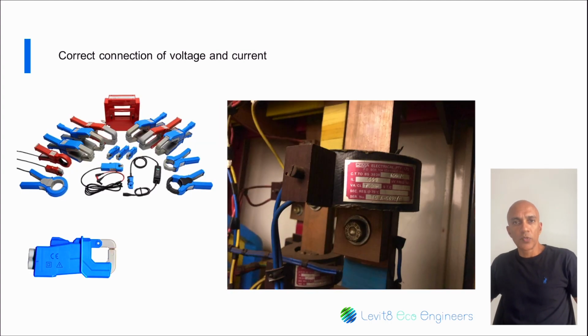The current connections would have a current clip-on CT or current transformer on the end of each phase cable. These are the CTs that would have to be placed around the relevant phase cable to be measured. The CT rating is crucial here, and one needs to ensure that the maximum current that the CT can handle is greater than or equal to the phase cable being measured. For this, one would look at the circuit breaker size of the feeder or the cable size.